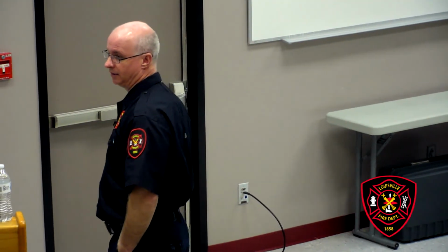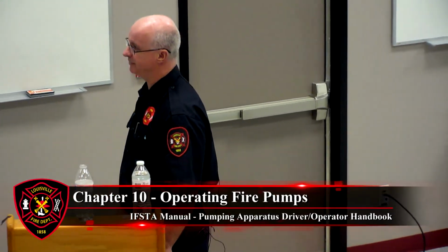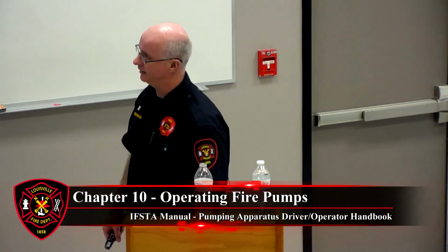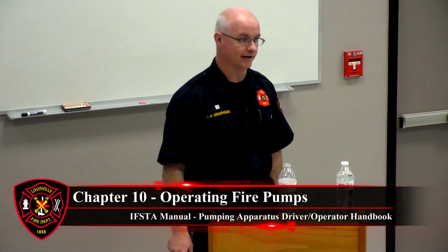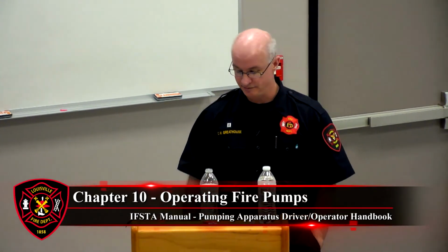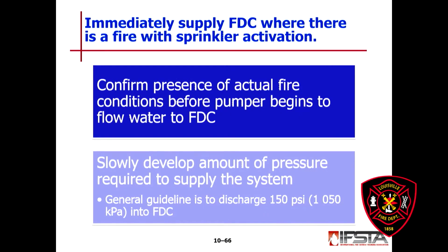We don't necessarily have to hook hoses up to them every time we make an alarm sounding, but once we get an indication that there's actually a fire, we need to be hooking into these fire department connections, these Siameses, laying out and establishing a positive water supply, and start pumping into these systems to make sure they're supported. The general guideline for a Siamese is 100 to 150 psi.